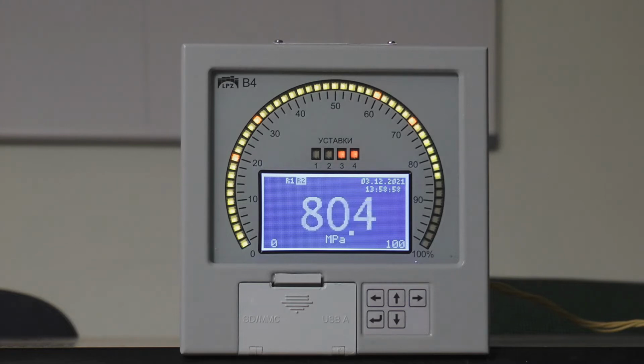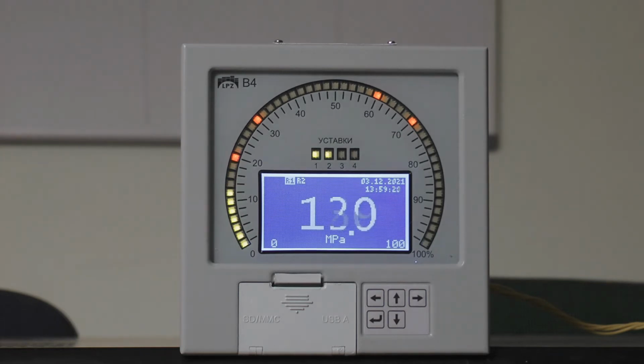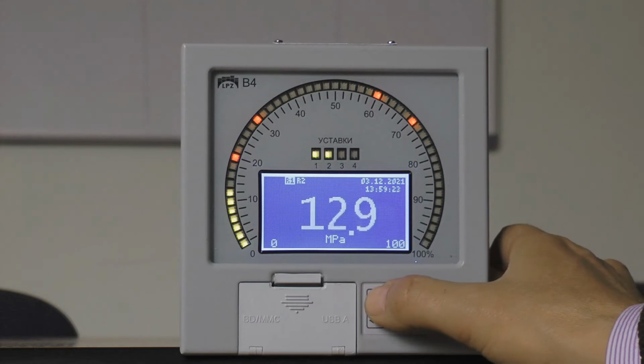When the signal increases and goes over set points number 3 and number 4, indicators light up. This instrument has 2 relays, but there may be 4 of them. Then each set point will correspond to its relay. As you can see, relays are set for the second and the third set points. When they are triggered, the relays close and open.